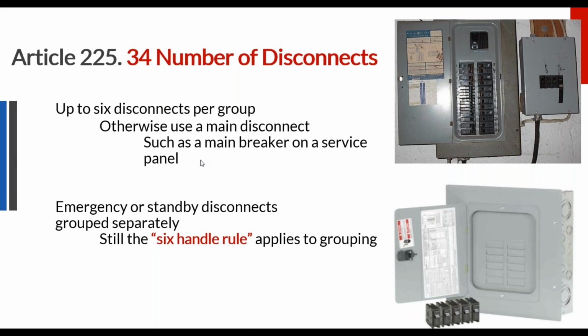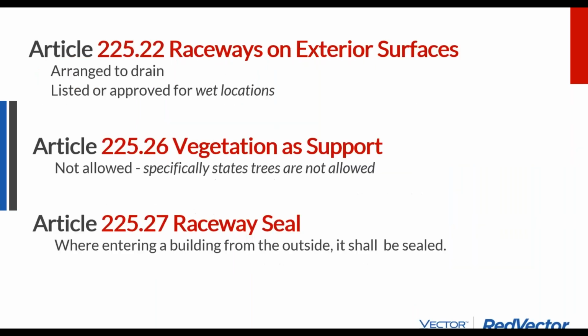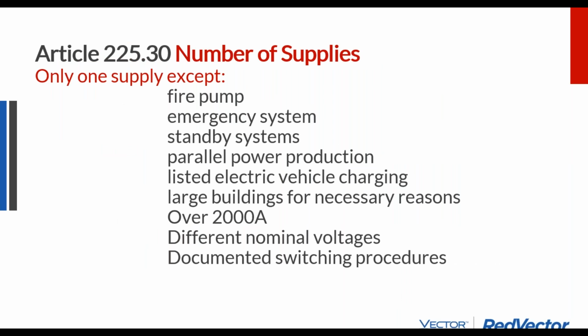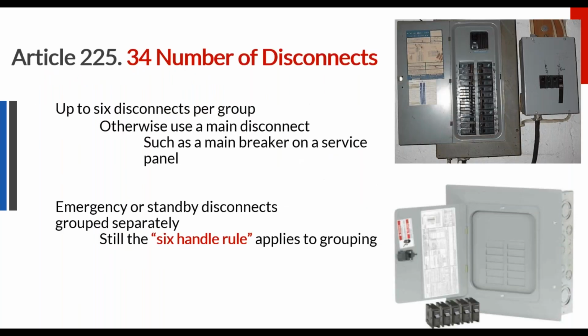So if you have an 800 amp service panel and you have 6 100 amp services coming off of it, they don't need to be wired together to be one master disconnect switch. But if you had more than that, then you would need a main disconnect switch for it. Now the thing is, every special group, your backup systems, your fire alarm systems, those are considered separate supplies, or can be considered separate supplies. And so you can apply this rule within groupings, but wherever there's one group of similar disconnect switches, if there's more than 6 of them into a panel, you need to have one switch you can throw to power them all down.